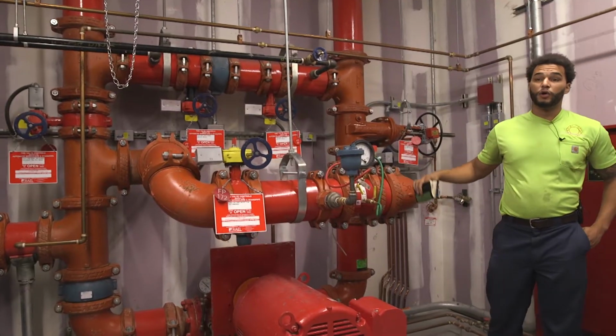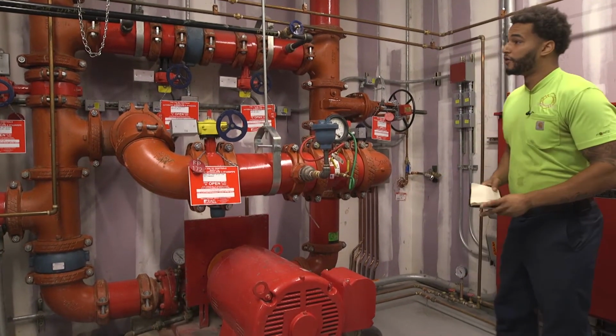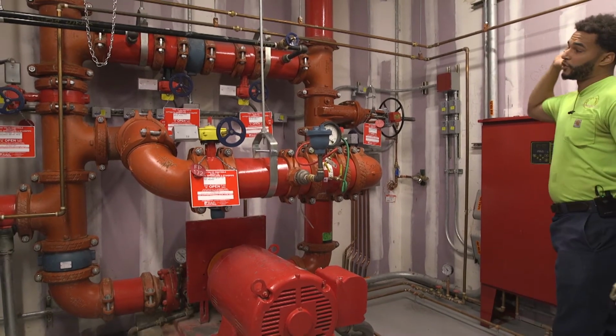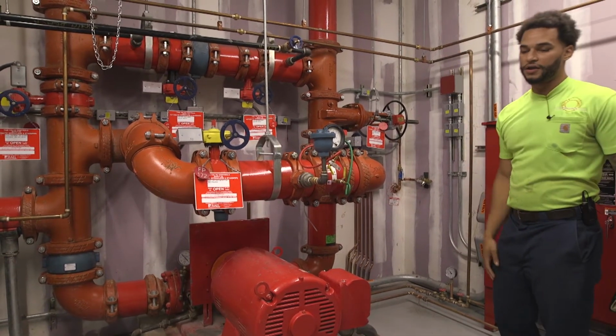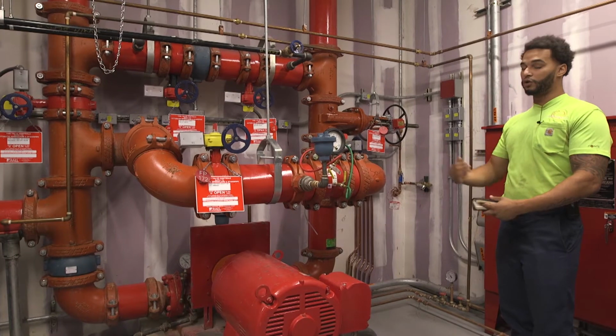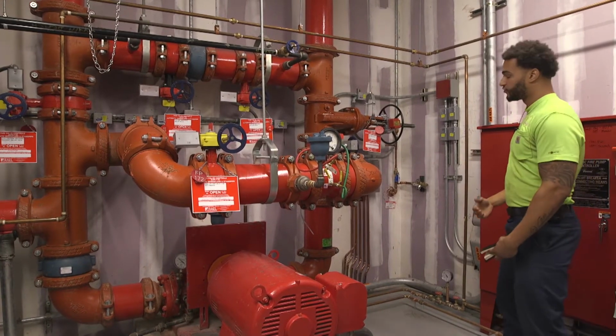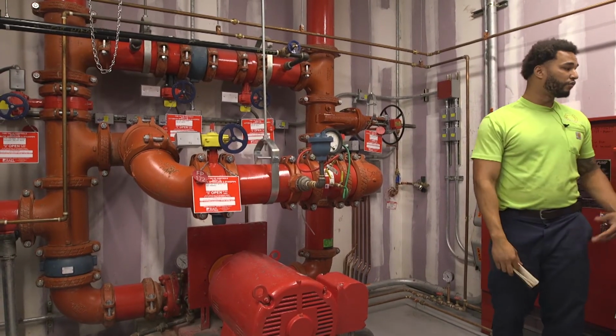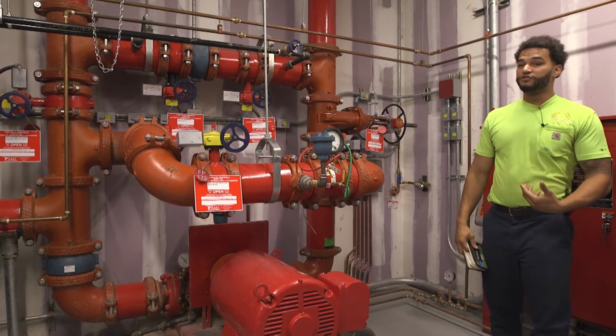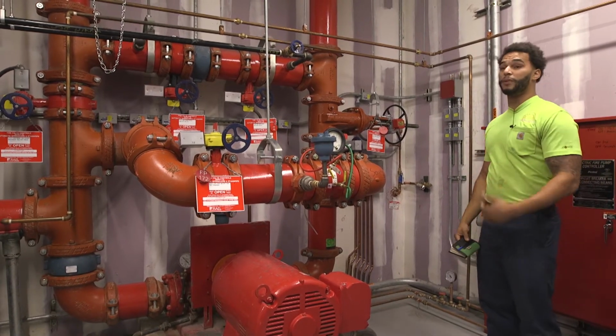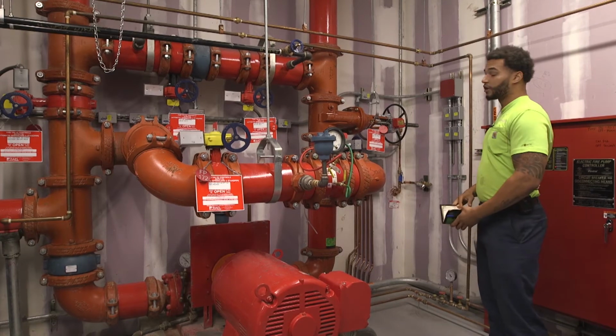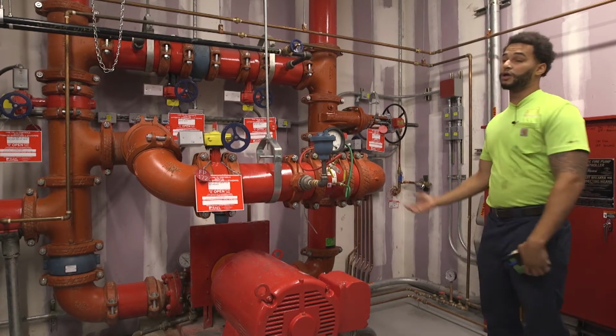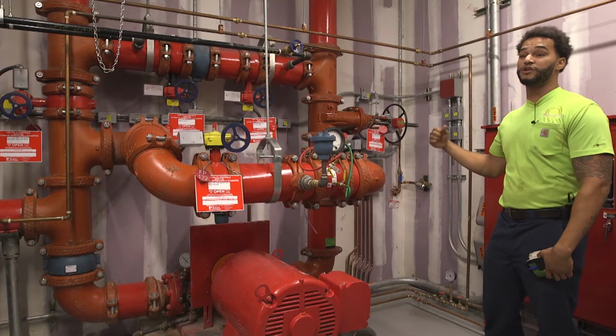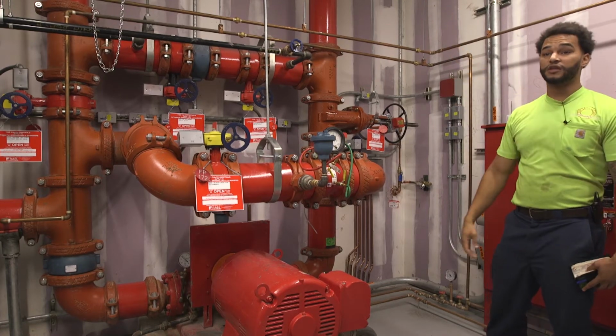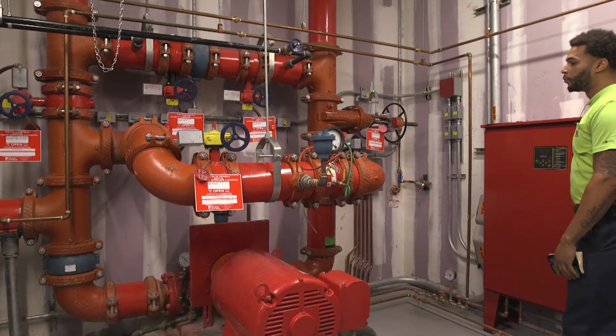The fire pump is not your full sprinkler system. It's only a component of your sprinkler system. If a sprinkler head was to go off at any certain floor, that means we will lose pressure in the system. If it's a slow leak, say somebody just tripped the valve, the jockey pump is going to slowly bring your system up to pressure. But if we're losing pounds by the second, where the jockey pump can't keep up, your fire pump's going to kick on, pressurize your system, and keep you protected where that sprinkler head is opened.